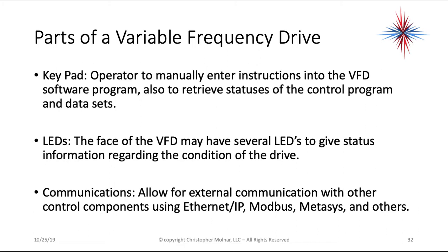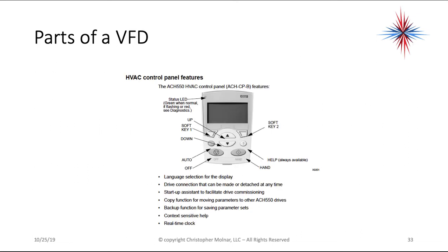You usually have a keypad. The operator can manually enter instructions into the VFD software program. It can also be used to retrieve statuses of the control program and data sets. You have LEDs. The face of the VFD may have several LEDs to give status information regarding the condition of the drive. You have communications. It allows for external communication with other control components using Ethernet/IP, Modbus, METASYS, and other proprietary standards.